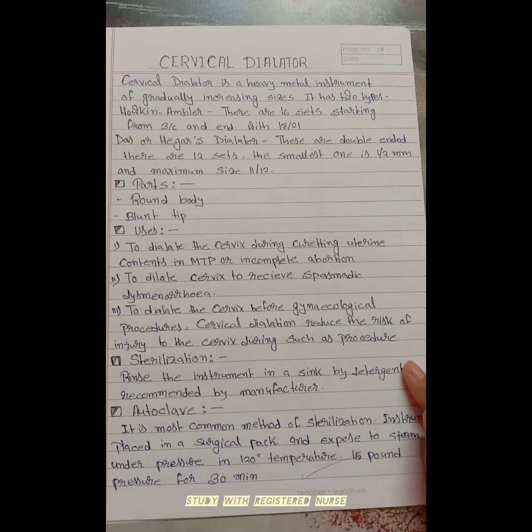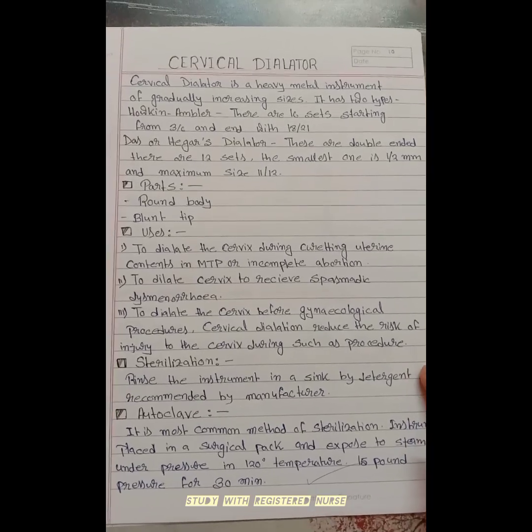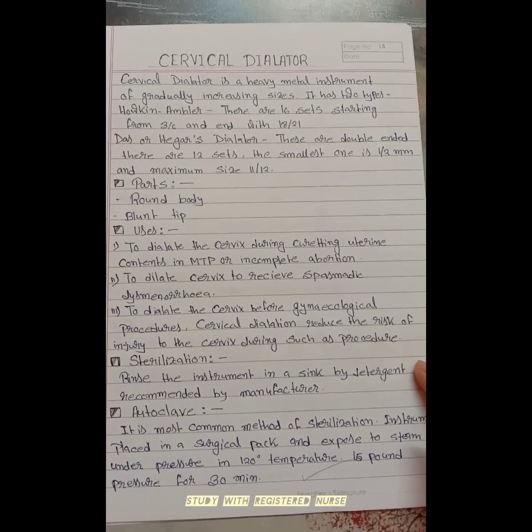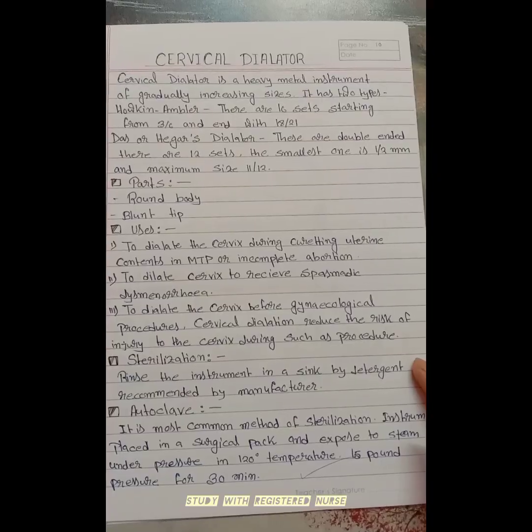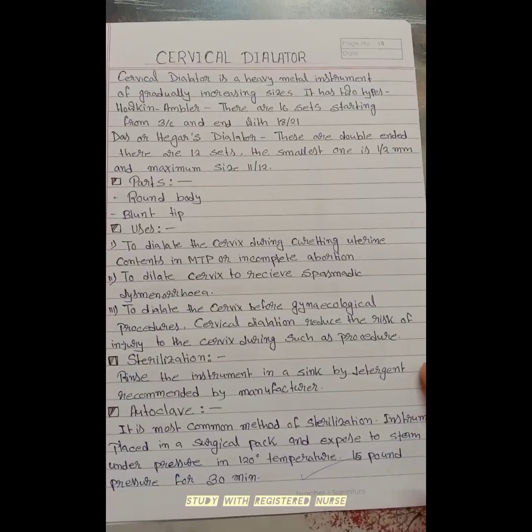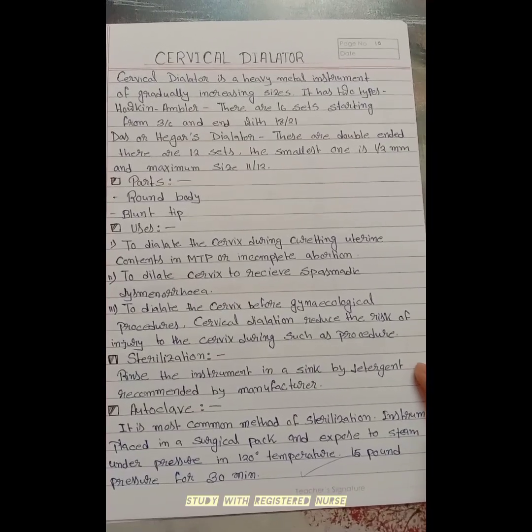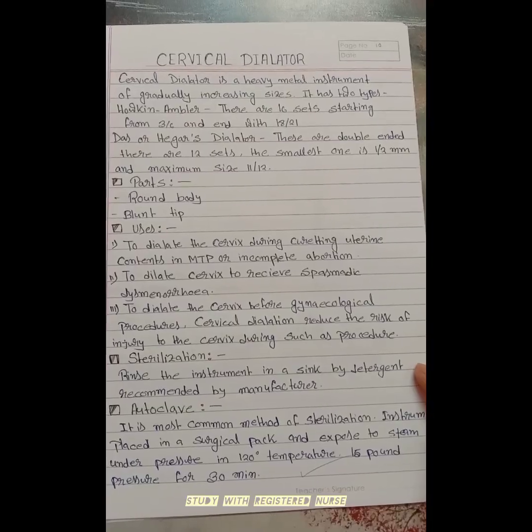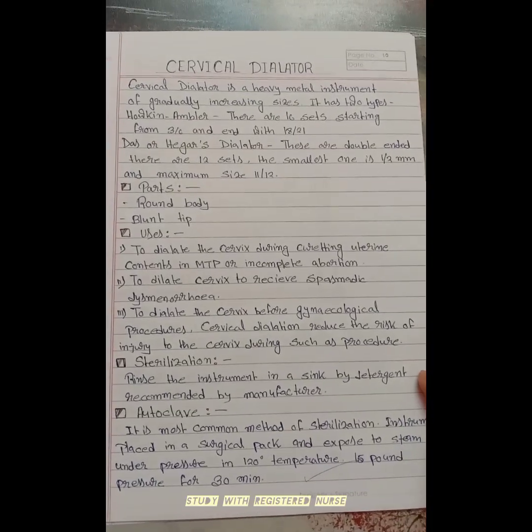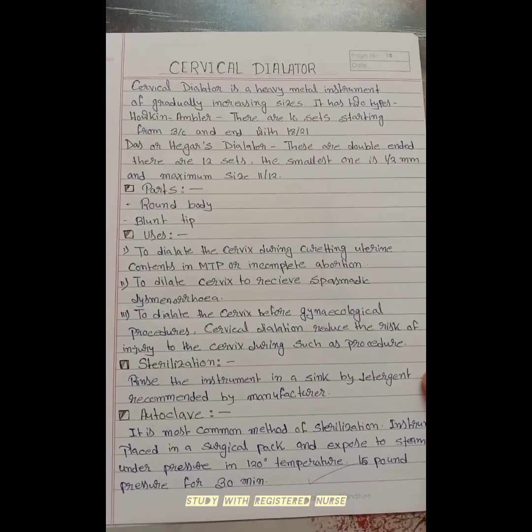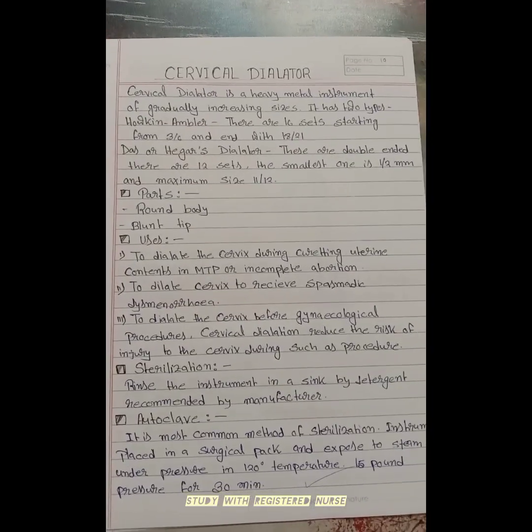Then I discuss the sterilization process. At first, wash with normal water and detergent recommended by the manufacturer, then wash with normal water and then place with the surgical pack and expose to steam at 120 degrees temperature, 15 pound pressure for 30 minutes.